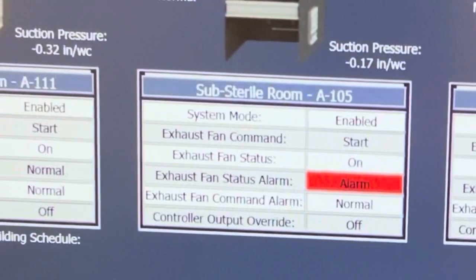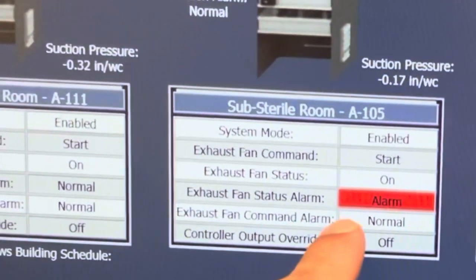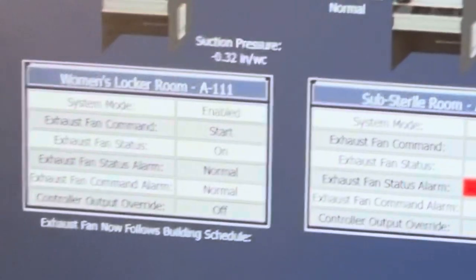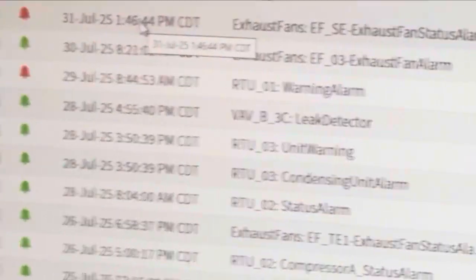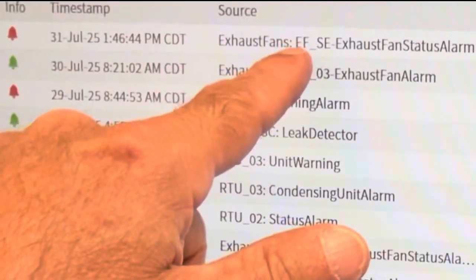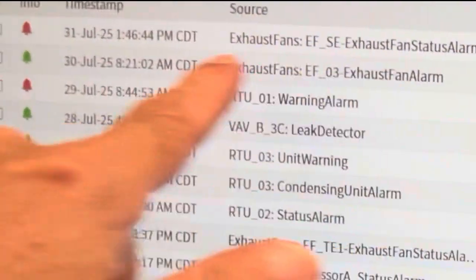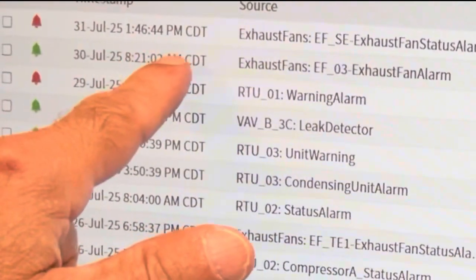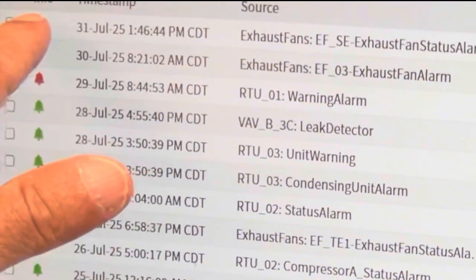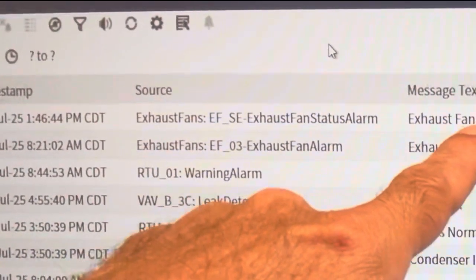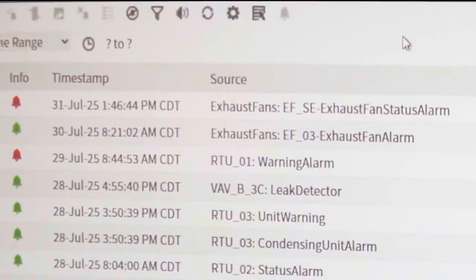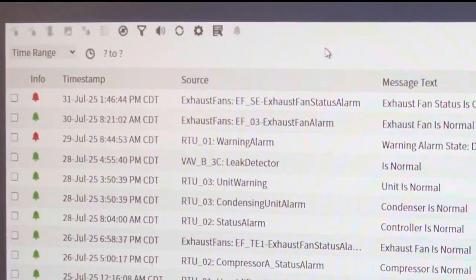Later on I may adjust that and see if the alarm goes away, but I might just wait till tomorrow, because I know for some reason there's a big time delay on these. If I go to the alarm log, I can see that exhaust fan when it came back. So here it is, exhaust fan SE. Exhaust fan normal. That was yesterday and this is today, so it's showing an alarm. Exhaust fan status is off when commanded on, but I know it's running. So I will follow up later. I don't have the answers to that, but I know physically the fan is operating and my room pressures have settled down.